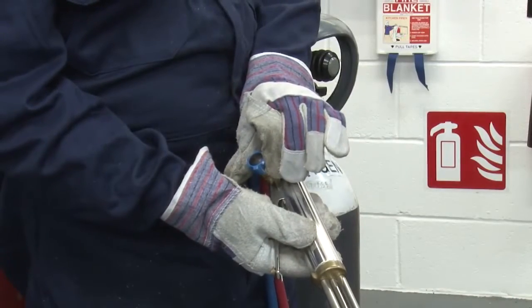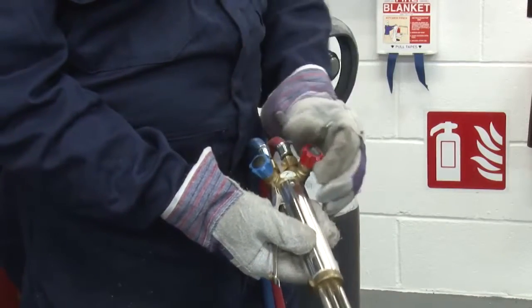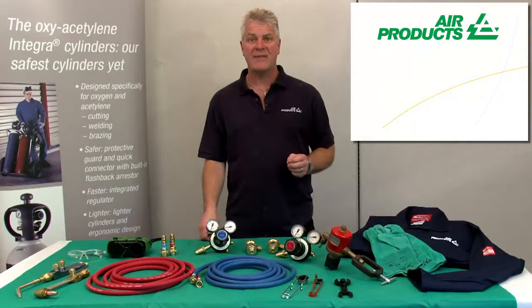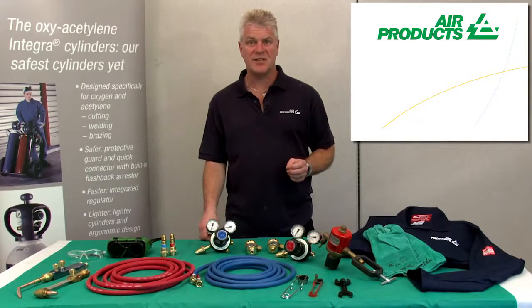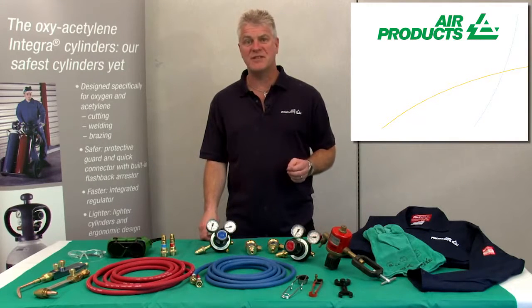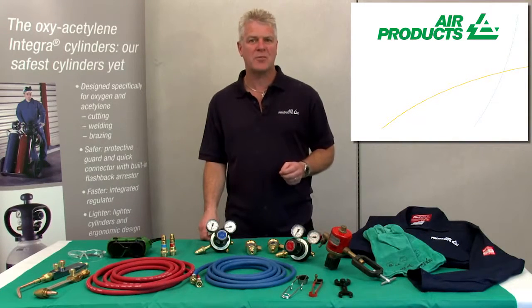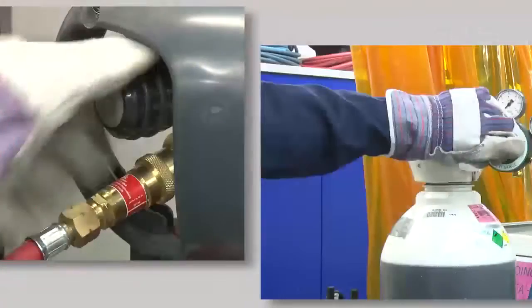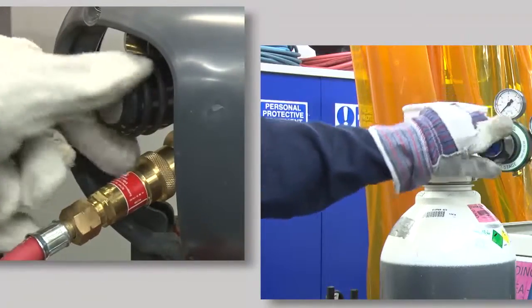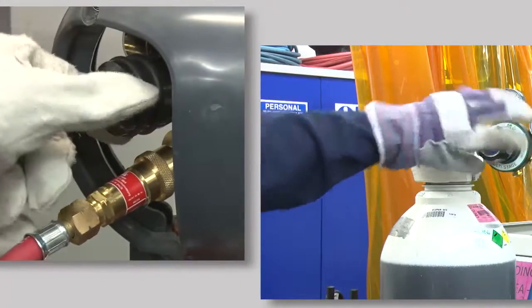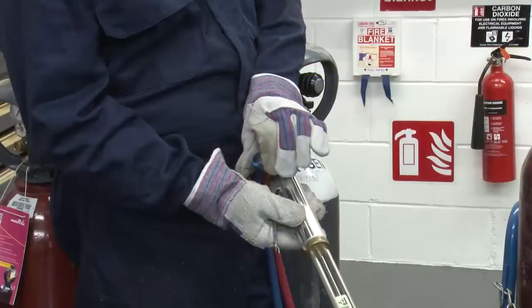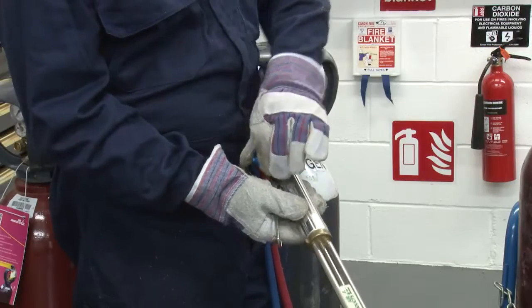This operation should only be carried out in a well-ventilated space. If this step is not carried out, there's a danger of flashbacks and backfires when lighting the torch. The lighting up procedure is described in detail on the Air Products website. The regulator pressure control knob should be closed, that's in the fully anti-clockwise position. Check that the torch valves are closed.